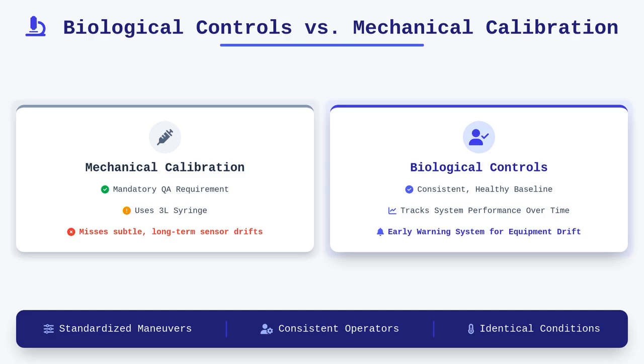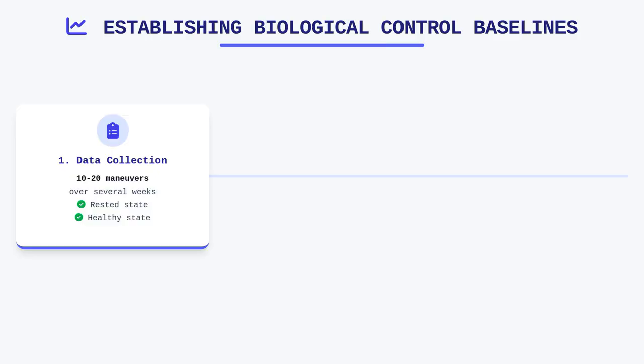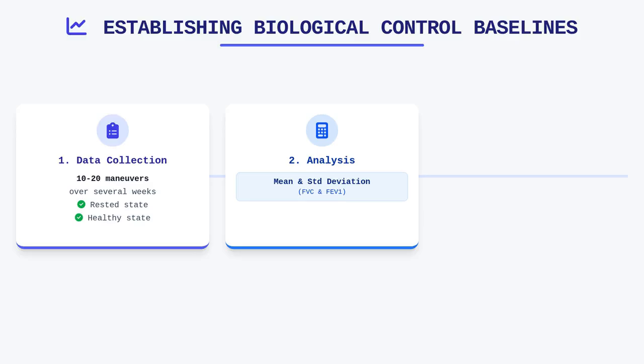You must ensure that these tests are performed under the same conditions, using the same technique, and preferably by the same operators to reduce noise in your dataset. To establish a baseline for your biological control subject, you must collect a series of at least 10 to 20 maneuvers performed over a period of several weeks in a rested and healthy state. Once you have this initial dataset, you calculate the mean and the standard deviation for key parameters such as FVC and FEV1 to define the target range for your ongoing quality control.